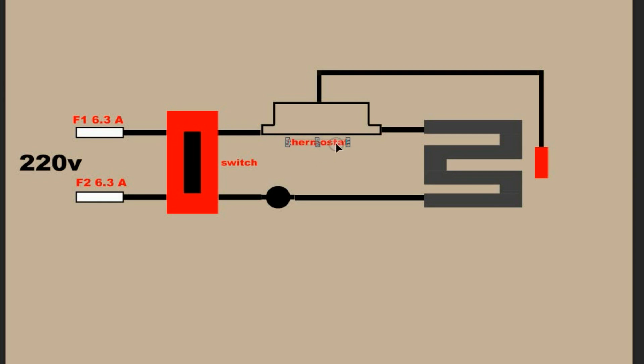And here is the NTC, or the negative thermal coefficient. The surface of this NTC should touch the body of the hydrocolator — this is an extra safety feature for the unit to avoid overheating.